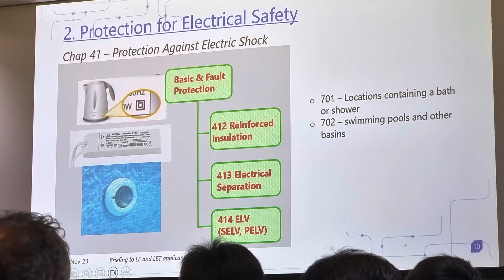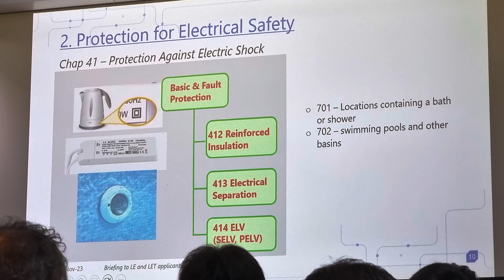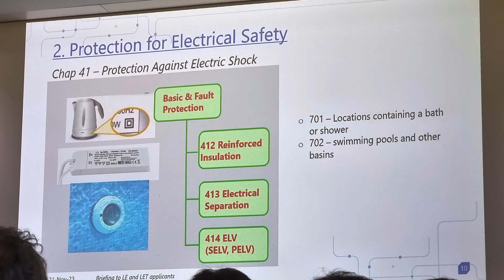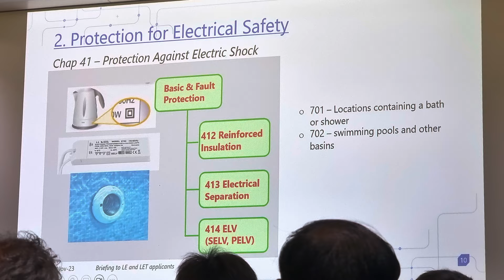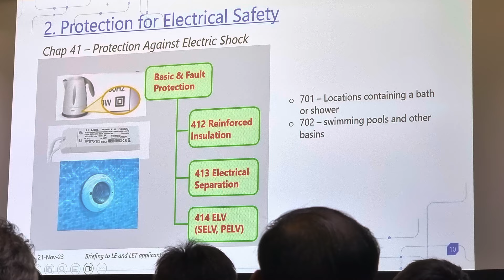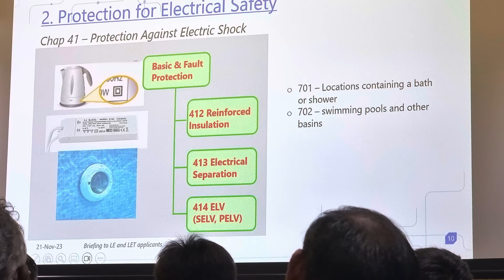Okay. Next, there will be a combination of these fault protections. These are important, especially in special applications. For example, the swimming pool. For example, the bathroom, where there's a shower, bathtub, etc. So you need basic fault protection, described in the code for installations, in 412. These are usually found in appliances and so on. But in 413 and 414, we talk about electrical separation. Electrical separation is important, especially in special environments. When the body is wet, resistance is low. So special attention is paid to make sure the person is still safe. So there's this SELV, which is a separated electrical source, to make sure that the voltage is low and there will be no chance of electric shock.